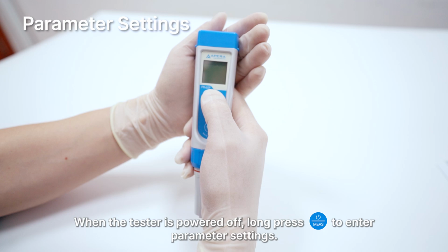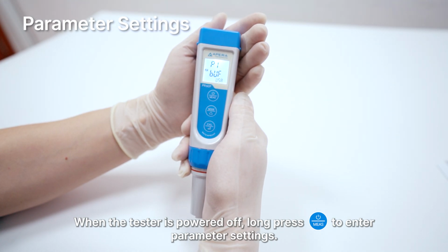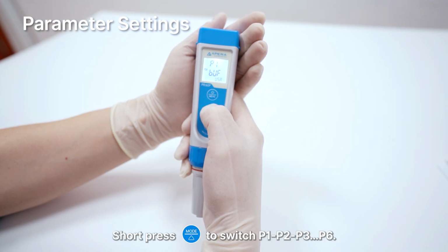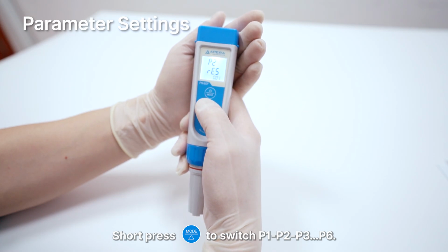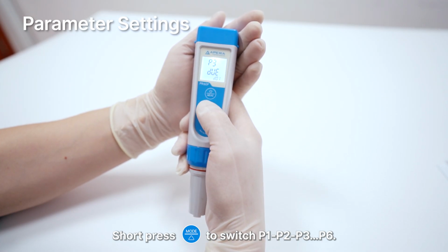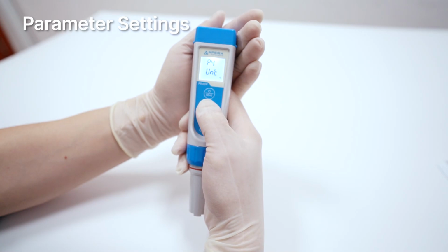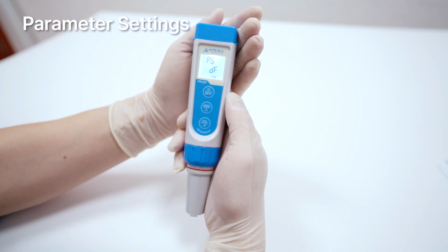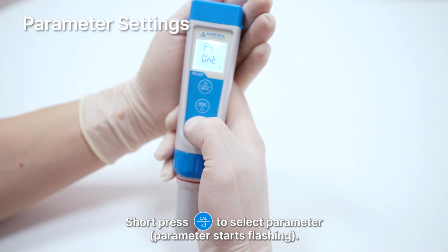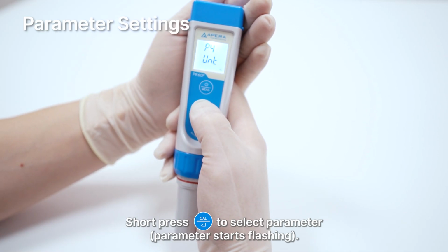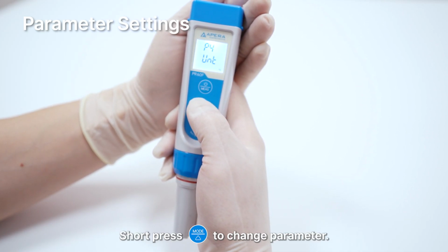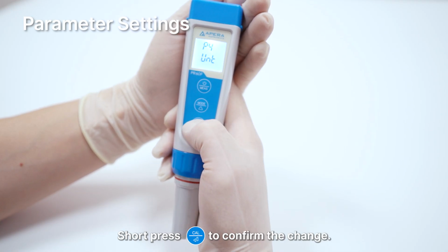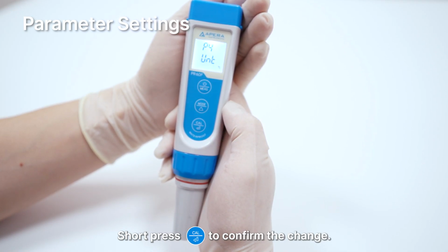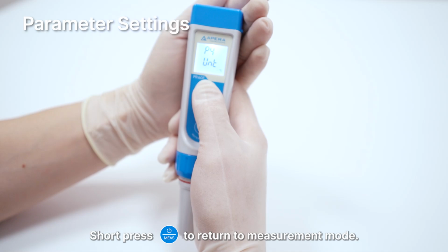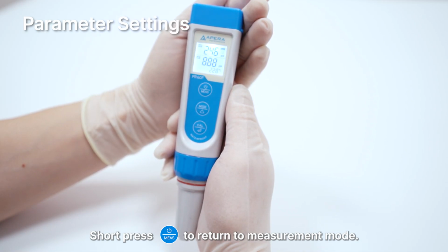Parameter settings. When the tester is powered off, long press the power on button to enter parameter settings. Short press the mode button to switch P1, P2, P3 to P6. Short press the confirm button to select parameter. Short press the select button to change parameter. Short press the confirm button to confirm the change. Short press the measurement button to return to measurement mode.